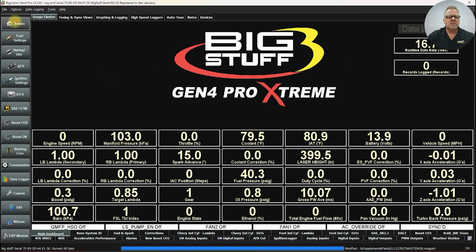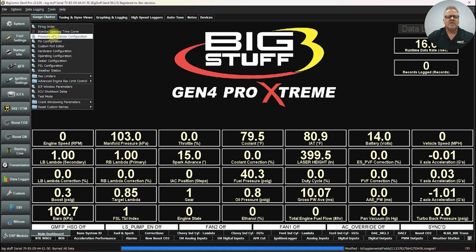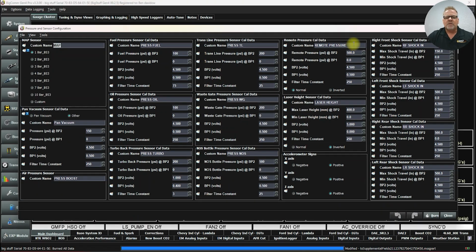If I close this out, I'll go to System, Pressure, and Sensor Configuration. Here you'll see that Remote Pressure name — again, that name can be anything you want. This is where you'll actually adjust the scaling for that input, in this case 0 to 500, or 4.5 to... This is just one more available input for you to use, instead of before when it was this Remote Accelerometer that wasn't being used on our system.